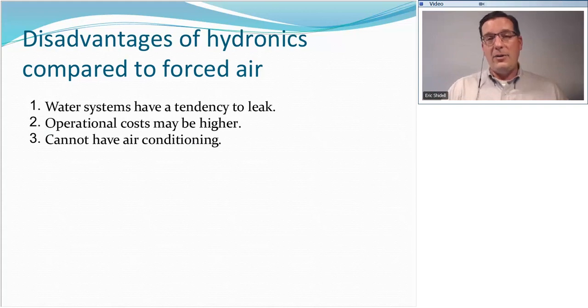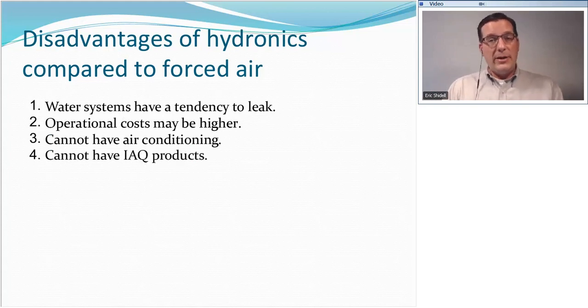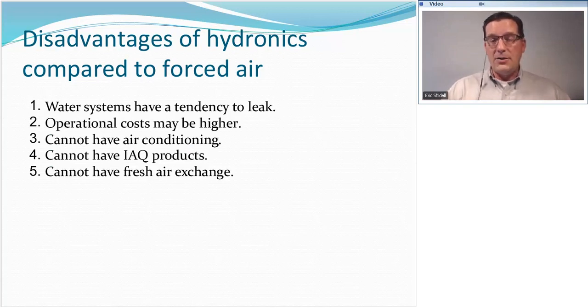You can't immediately put air conditioning onto a hydronic-only system, because air conditioning, by its very name, needs air. We need air ducts. So that's a bit of a disadvantage. If you want to have a home that has both a hydronic heating system and air conditioning, you're going to have two completely independent distribution systems, and that leads to higher installation costs. To go along with that, indoor air quality products like air filtration, humidification, and ventilation don't exist alongside or within a hydronic system. They have to be added to the building separately with their own duct system, fan system, and all of that. Also, no fresh air exchange.